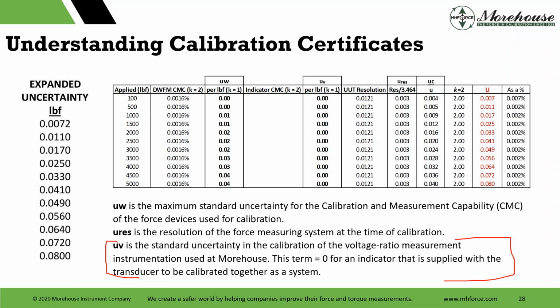In this example, we did not use the voltage, so we simply set that to 0 up here. Look, UV indicator 0, 0. So what we're going to do here is typically take all of these contributors and take the sum of the squares of these. So we're going to say 100 times 0.0016. We're going to take UW, then the resolution, URes, and UC, and we're going to sum the squares of these.